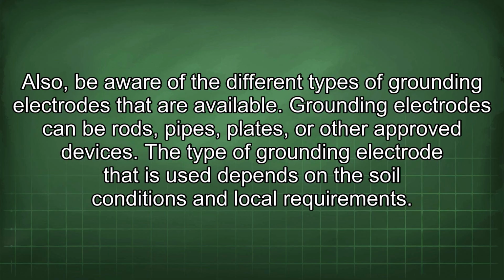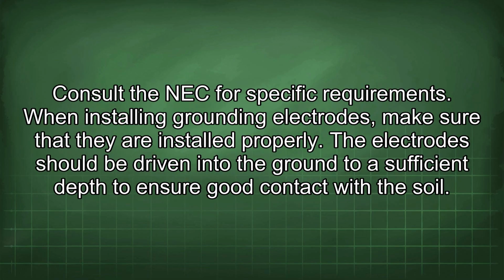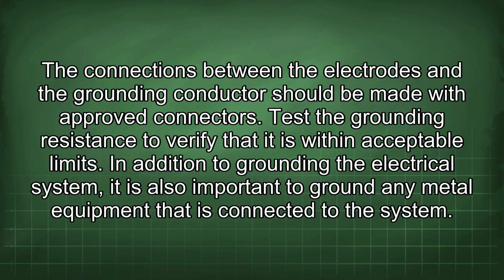Also, be aware of the different types of grounding electrodes that are available. Grounding electrodes can be rods, pipes, plates, or other approved devices. The type of grounding electrode that is used depends on the soil conditions and local requirements. Consult the NEC for specific requirements. When installing grounding electrodes, make sure that they are installed properly. The electrode should be driven into the ground to a sufficient depth to ensure good contact with the soil. The connections between the electrodes and the grounding conductor should be made with approved connectors. Test the grounding resistance to verify that it is within acceptable limits.